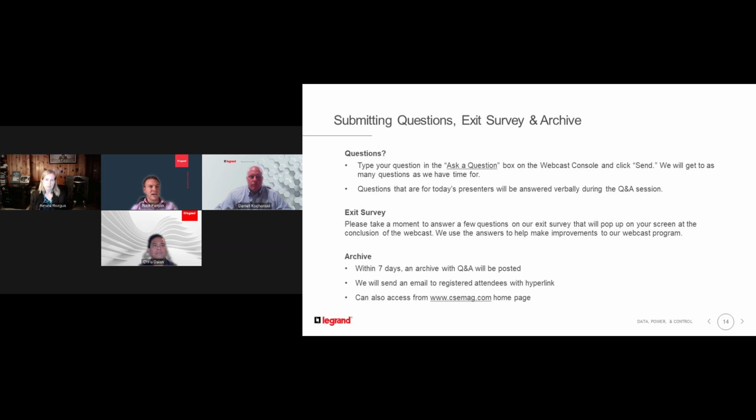Now, granted, as an engineer, I don't want to have just one way in and no way out, right? So there is a way out, right? So let's say you guys did specify something and you're on site and your project manager says, oh man, I screwed up. This should be 5 foot less, right? There is a way out. You can call Starline up, any other manufacturer. You should be able to cut that in the field with a technician, right? We have a series of saws that travel around in a plastic buckhorn for this exact situation, where we could help get people out of a bind if, in fact, you have some busway on site that maybe is a little bit longer than expected.